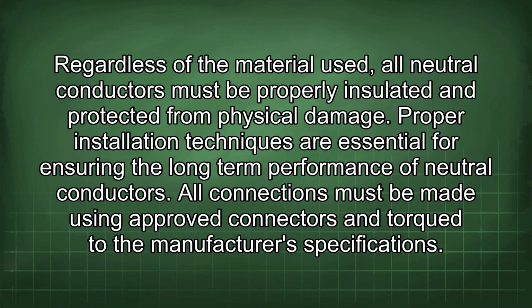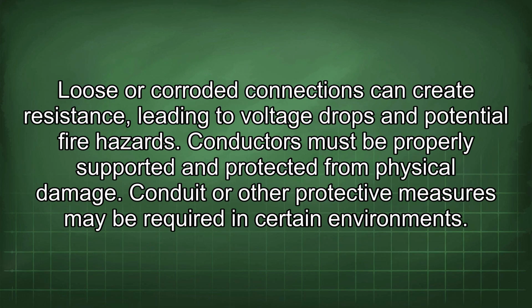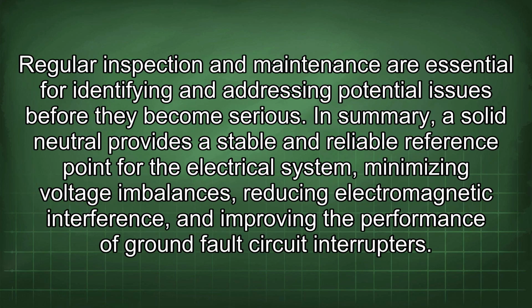Proper installation techniques are essential for ensuring the long-term performance of neutral conductors. All connections must be made using approved connectors and torqued to the manufacturer's specifications. Loose or corroded connections can create resistance, leading to voltage drops and potential fire hazards. Conductors must be properly supported and protected from physical damage. Conduit or other protective measures may be required in certain environments. Regular inspection and maintenance are essential for identifying and addressing potential issues before they become serious.